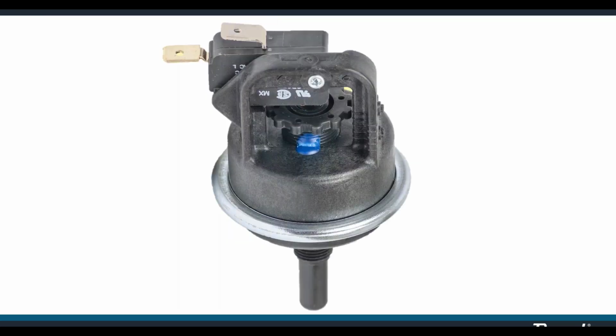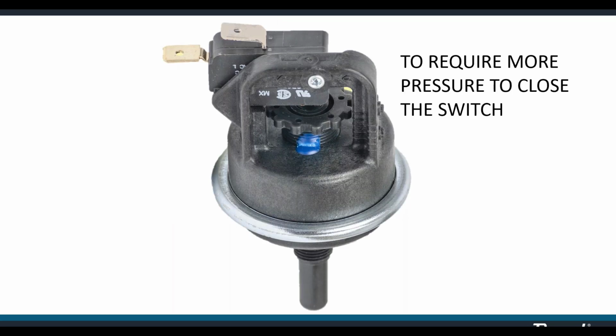Turning this adjustment wheel clockwise will cause it to require more pressure to close, as might be necessary when the heater is located below water level. Which of course means that turning it counterclockwise causes it to require less pressure to close, like for an elevated installation. All right. I don't see any questions on the board, so I'm just going to keep rolling. We're going to talk about air.